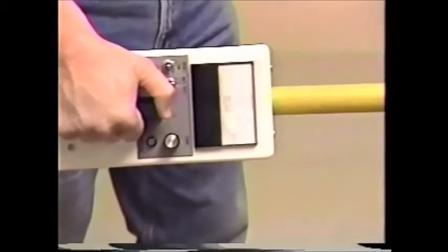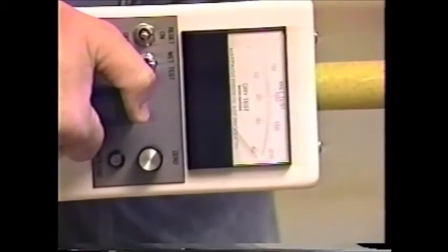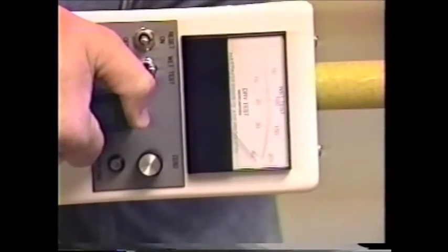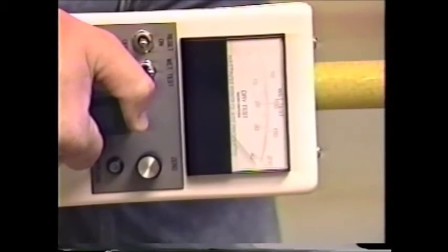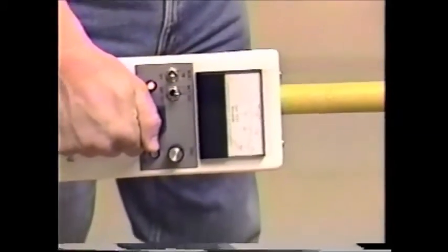Surface contamination, surface conditions, cracked fiberglass, gouges, and deep scratches can cause a tool to fail the wet test. Most of these defects can be addressed with proper cleaning.